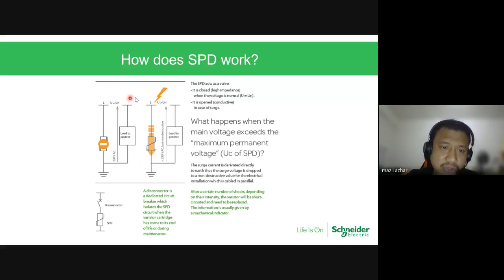Maximum voltage is equal to the system. But what happens when the main voltage exceeds the maximum permanent voltage? It will automatically become a short circuit. Instead of the surge traveling to your loads, it will divert directly to earth. This is where it comes into play. And normally for SPD, let's say 230, right? Normal operating is 230, and then normally for SPD, the maximum permanent voltage is normally like 275 or 260, depending on the manufacturer. So let's say the voltage exceeds 275, then it becomes a short circuit instead of an open circuit.